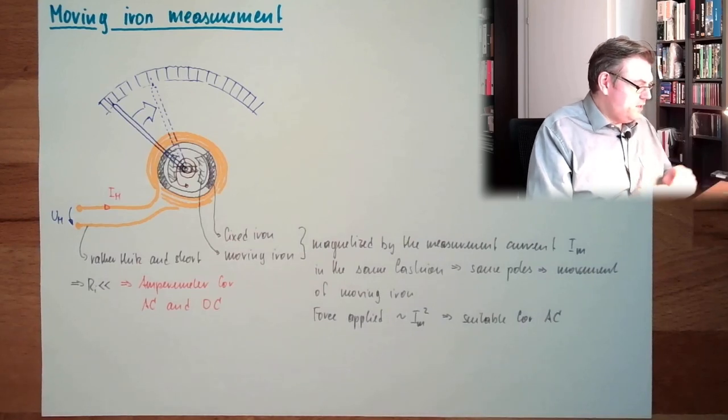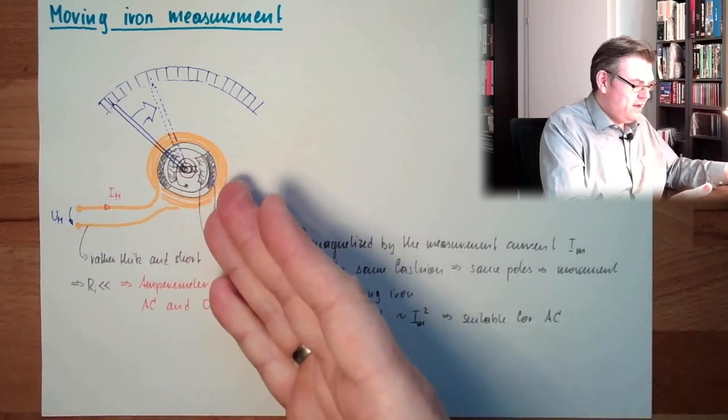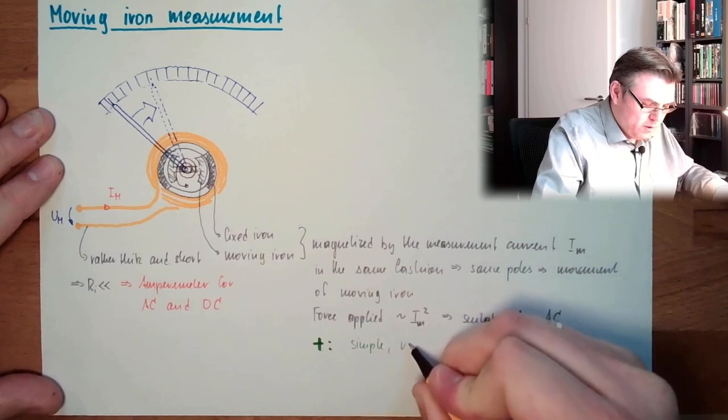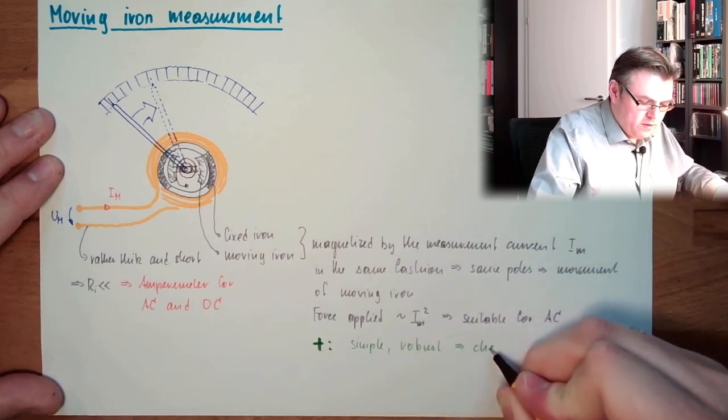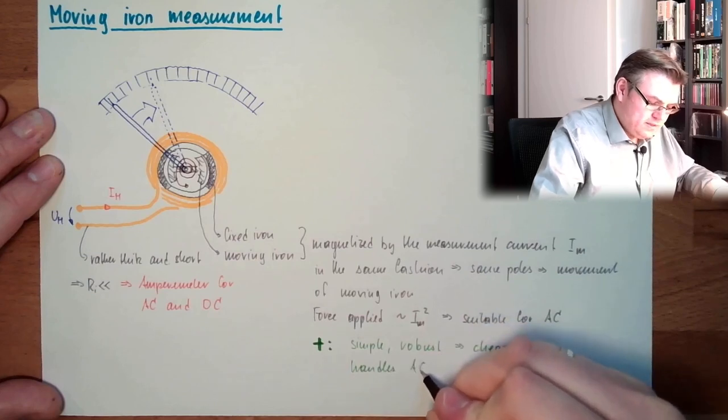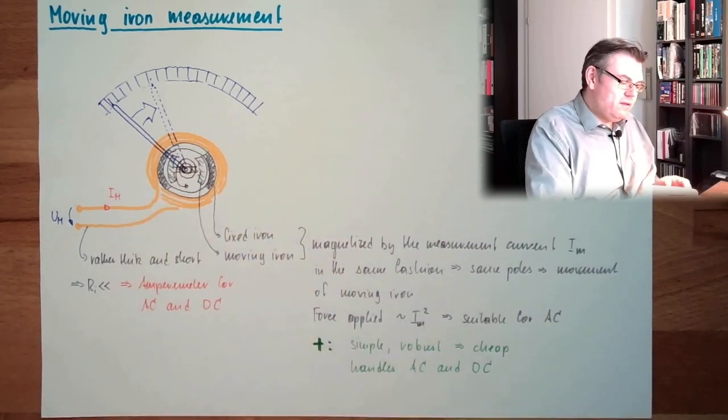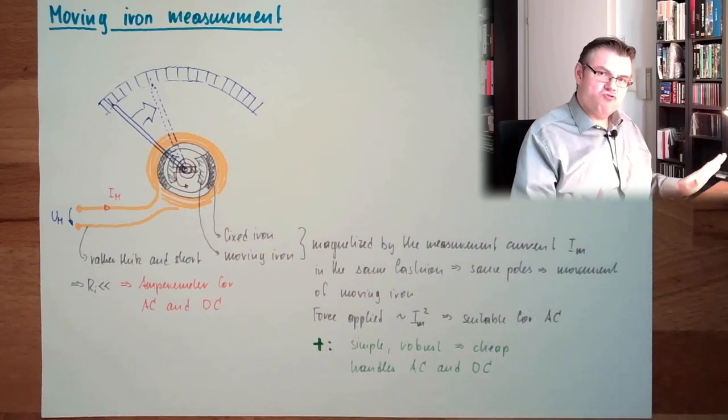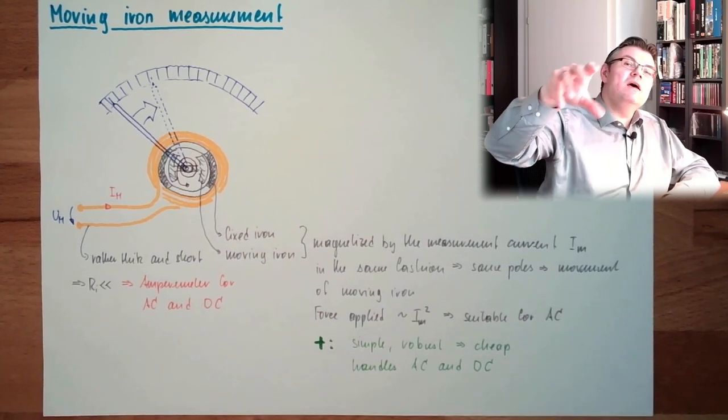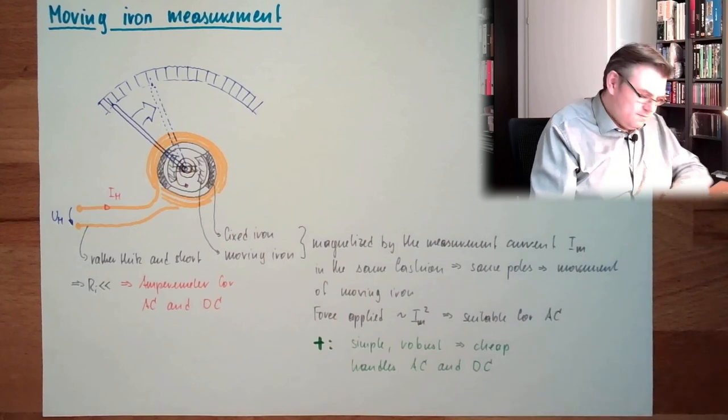So what is the advantage now? The moving part is rather simple, so it's simple and robust, so it's relatively cheap, alright? And we can handle AC and DC. And we can also adapt the wire and so on. We can do ampere meters, we can do voltmeters, great! This is actually the reason why a lot of these built-in, cabinet built-in measurement devices are moving iron measurements, because they are simple, robust, cheap, and so on.